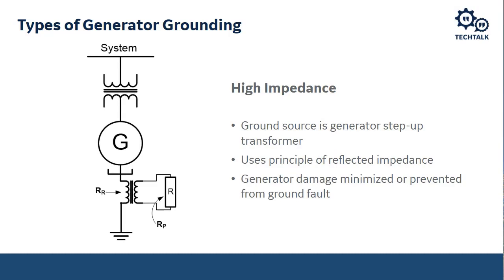The next and one of the popular grounding methods, especially for larger generators, medium to high megawatt rating, will see designs for high impedance grounded, because that's going to be our more important asset in the station, and we don't want to subject it to large amounts of ground current. We want to engineer it so that when there is a phase to ground fault, we can easily detect that phase to ground fault, and at the same time not damage the equipment. So typically what we do, as I mentioned, is we use a grounding transformer. And as I previously mentioned, depending on the selection of that resistor and the winding ratio of that transformer, that secondary impedance gets reflected to the primary, and we can then engineer that ground fault current.